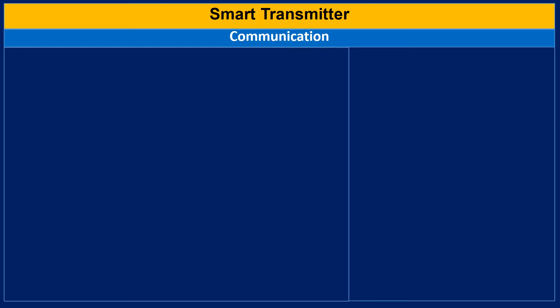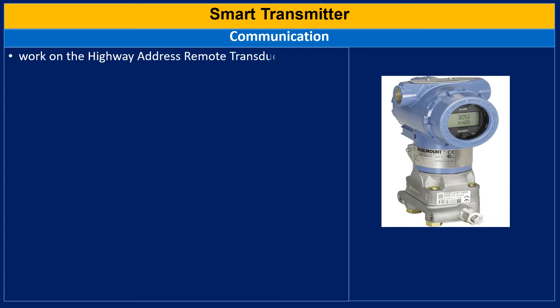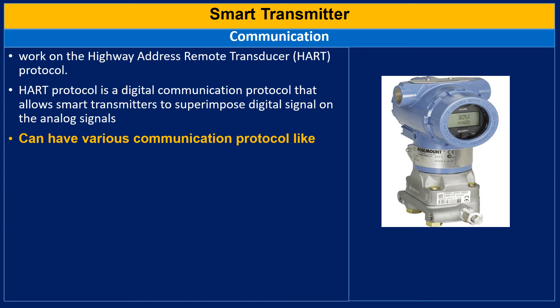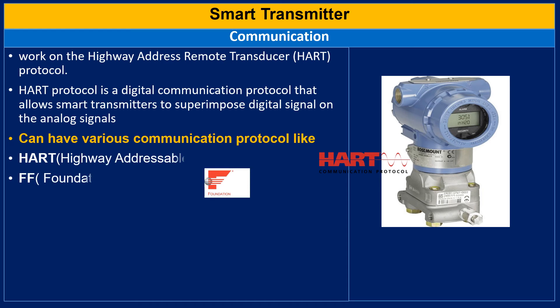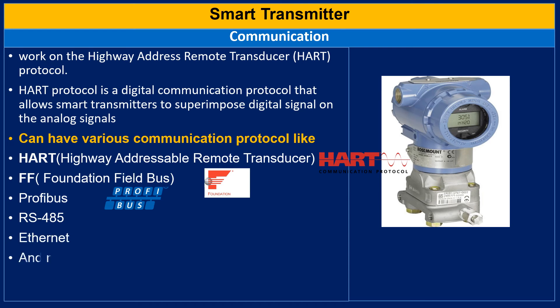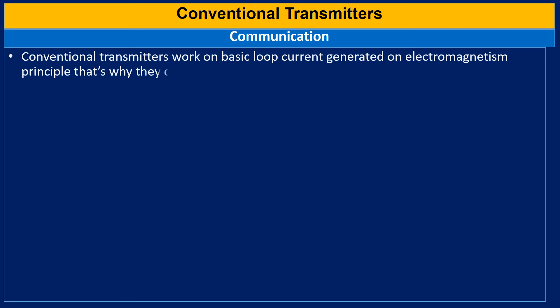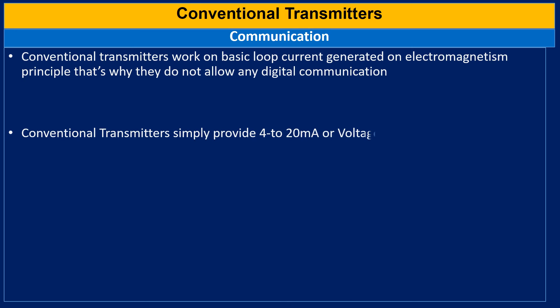Comparing both transmitters for communication: smart transmitters work on the Highway Addressable Remote Transducer, or HART protocol. The HART protocol is a digital communication protocol that allows smart transmitters to superimpose digital signals on analog signals. Smart transmitters can support various communication protocols like HART, Foundation Fieldbus, Profibus, RS-485, Ethernet, and many more. Conventional transmitters work on the basic loop current generated on the electromagnetism principle, so they do not allow any digital communication and simply provide a 4 to 20 mA or voltage signal with no other communication protocols.